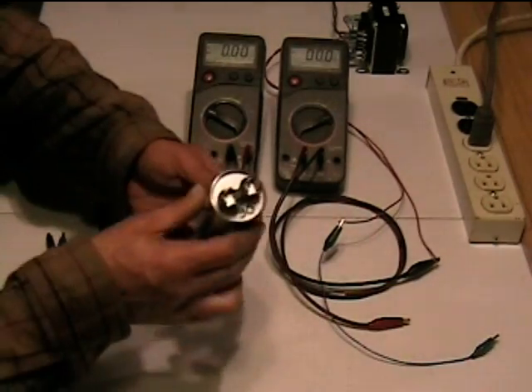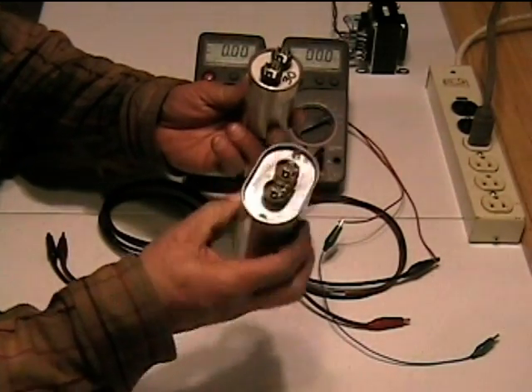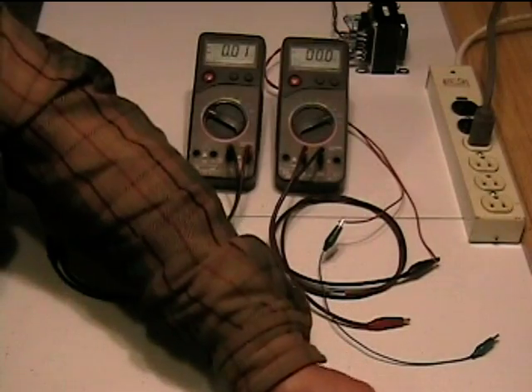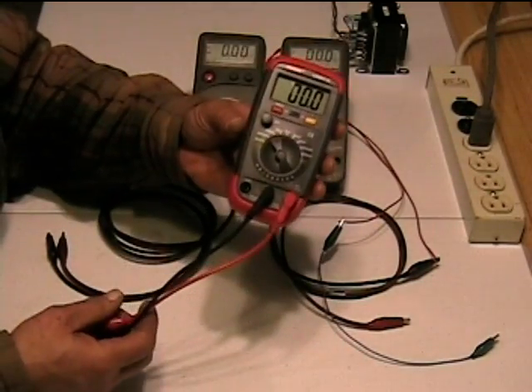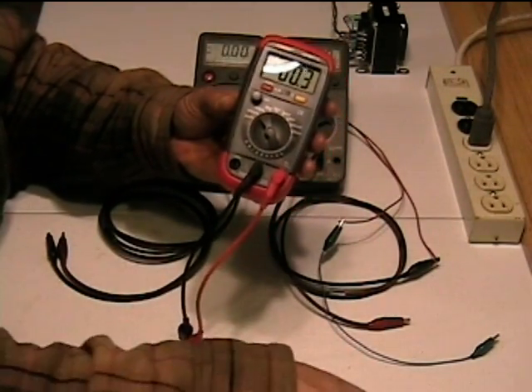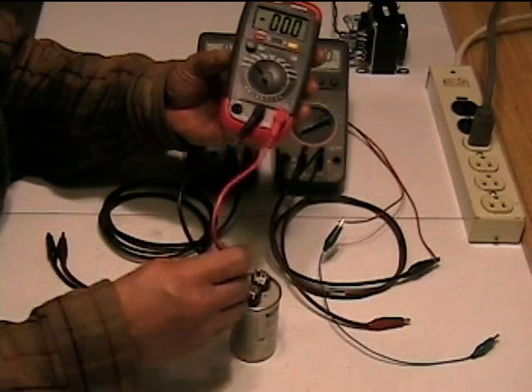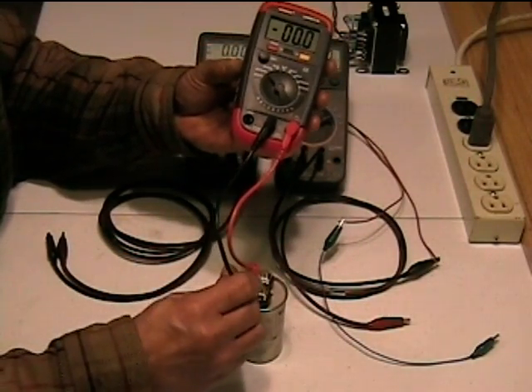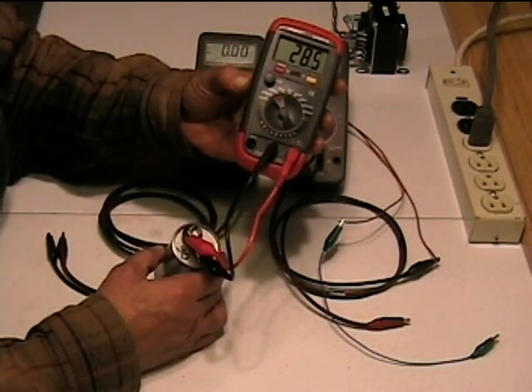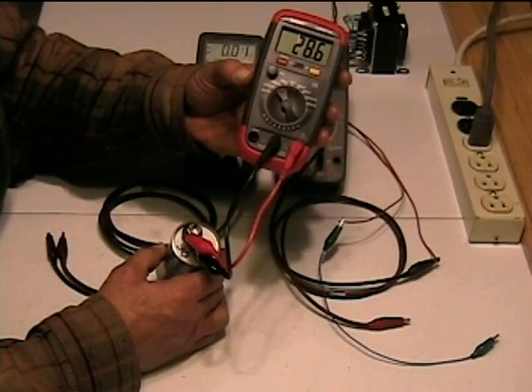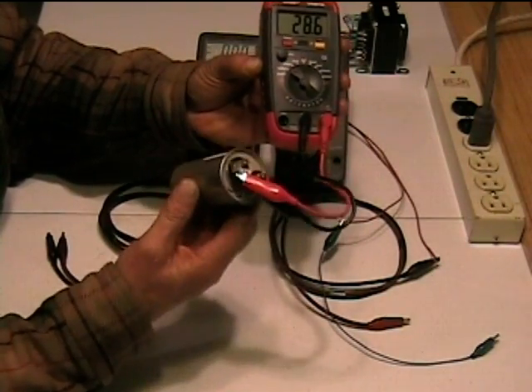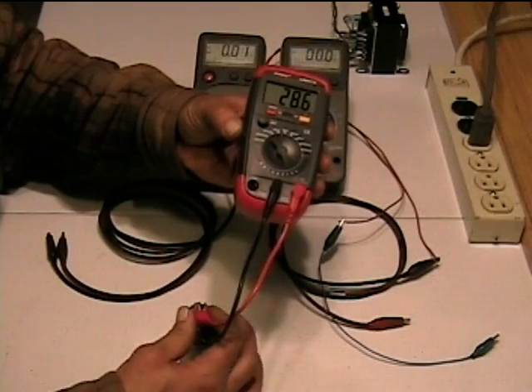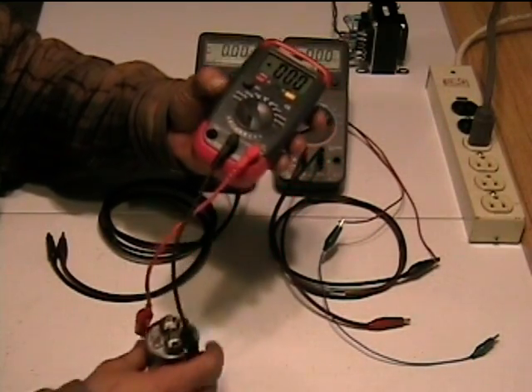If you need to test a capacitor like this or this, something you might find in a motor or an HID light fixture, and you happen to have one of these handy capacitor testers, it's a no-brainer. You just connect the meter across the capacitor and read the display. This one says 28.6 microfarads, which is about right for this 30 microfarad capacitor. So we know the capacitor is good. That's well within its tolerance.